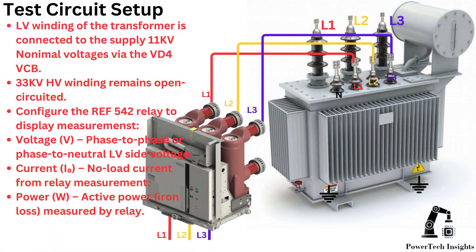Test circuit setup: the LV winding of the transformer is connected to the 11 kV nominal voltage supply via the VD4 VCB. The 33 kV HV winding remains open-circuited. Configure the REF 542 relay to display measurements: voltage — phase-to-phase or phase-to-neutral LV side voltage; current — no-load current from relay measurement; and active power measured by relay.